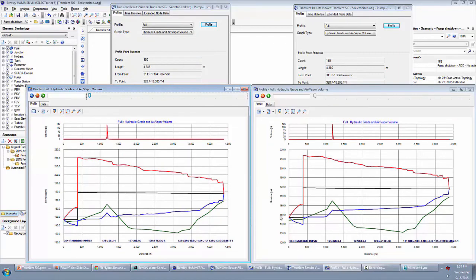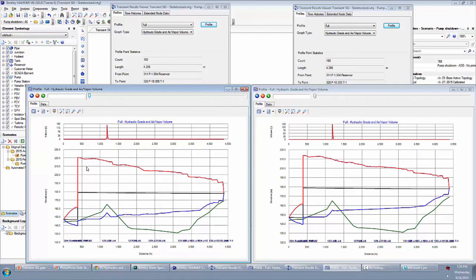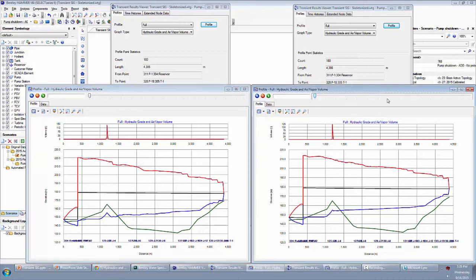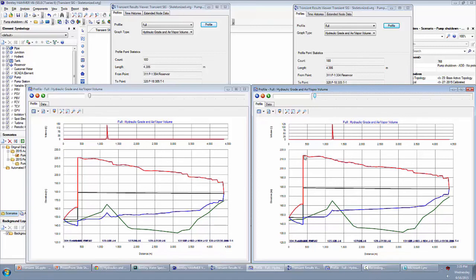Looking at the envelope, one thing I noticed is that the maximum hydraulic grade on the left side, which is the average day demand case, is about 220 meters over on the left side. Vapor pocket about 130 liters maximum. When we look at the peak hour demand, looks like things are a little bit better. Maybe about 215 for our maximum over here, a little bit less on the vapor volume.